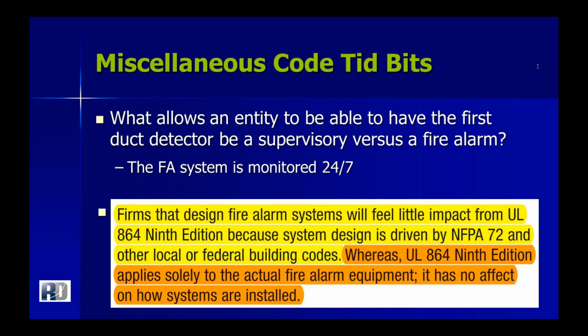Right, and like Dave had discussed in the presentation earlier, UL 864 discusses the devices, not so much how the systems are installed or wired. And, in the state of Wisconsin, using the state as an example, they believe that the controls are wired fail-safe. So when they're fail-safe, the dampers are going to go closed. That's all that has to happen. They don't have to be commanded open. They only have to be closed. So if something bad happens with the control system, someone cuts a wire, a fuse blows or whatever, the damper closes and fails safe.